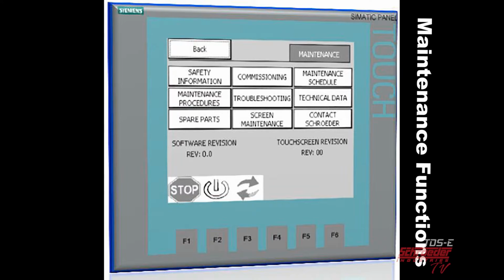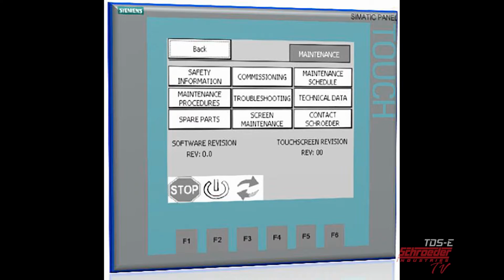The Triton maintenance screen allows the user to review select sections of the user's manual on the touch panel. Safety information provides basic safety information and instruction the user must follow while operating the Triton. Maintenance schedule provides the user the schedule that needs to be followed to ensure correct maintenance. There are inspection and maintenance schedules in the following categories: general, fluid filter, electrical, functional test, and drain spray pumps. Maintenance procedures provide the user with step-by-step maintenance procedures to follow to ensure correct maintenance.